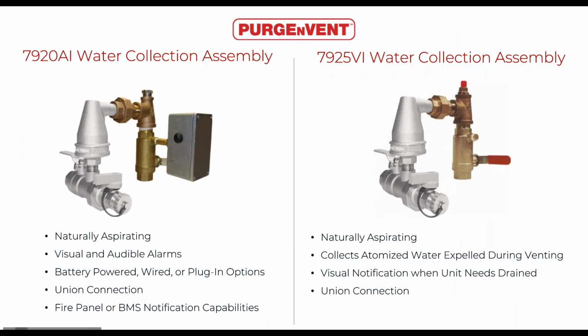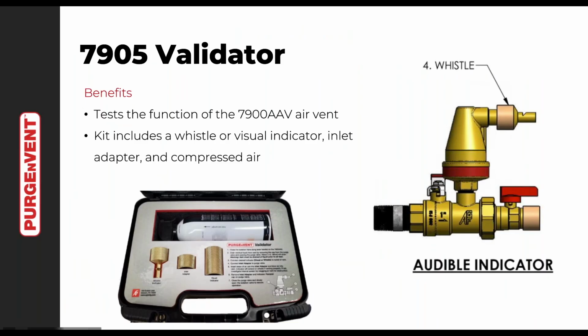We do offer both mechanical as well as electronic sensing devices that you can locate on our air vents to tell you if they're working properly. We offer the 7920 AI, a carryover from our collect and drain product line. This attaches directly to the outlet of the air vent, and the air will release out of this. If there is any failure in the air vent working properly, it will chirp and blink and tell you to come service it. We offer that as an electronic option, and then we offer a mechanical option with our 7925. This will give you a visual indication that the air vent is not working properly and needs some maintenance.